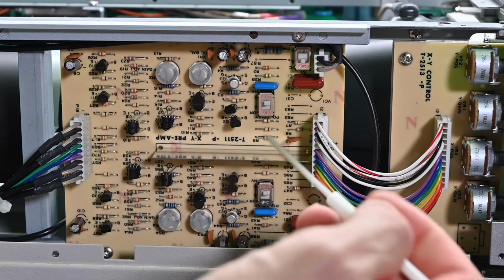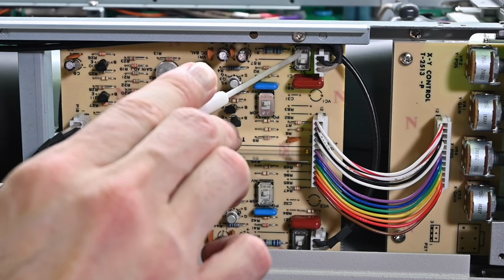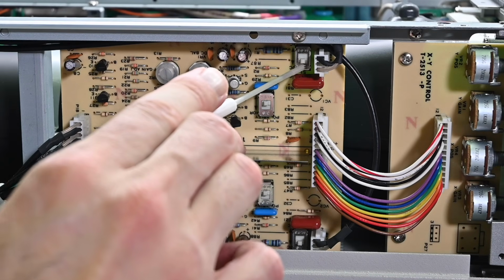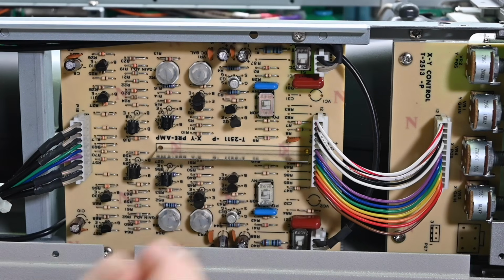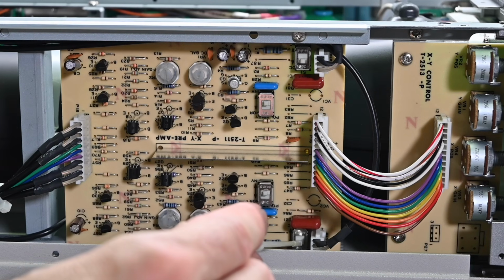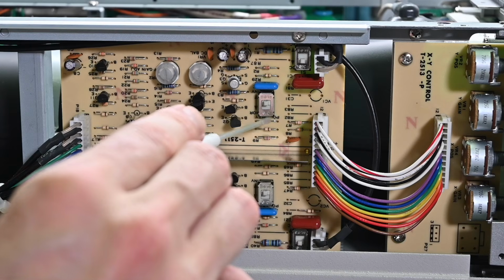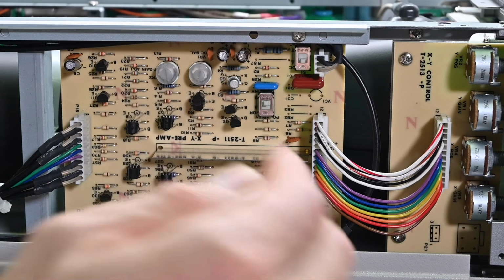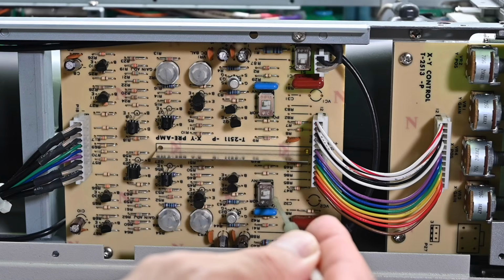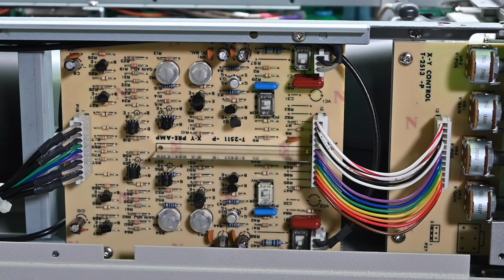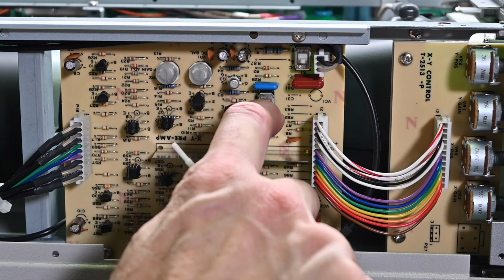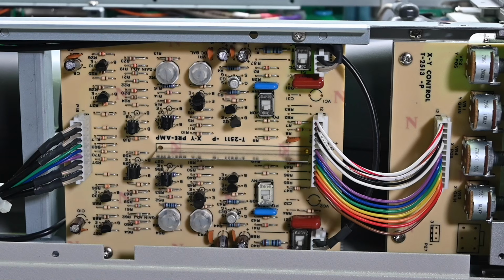But starting with these switches, this switch is coupling, so it's AC or DC, and it's in the DC setting, so direct coupled. That's fine, I would want that. And same with the switch down here, it's on the DC setting. This switch says invert and normal, and this one is invert and normal. Both switches are on the invert position. I would actually think maybe they should be on normal. I'm not entirely sure, but I'm going to go ahead and move them down to normal, like that. At least we'll start with that and see how it functions.